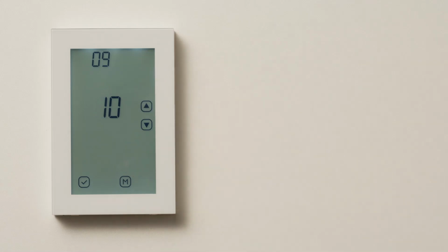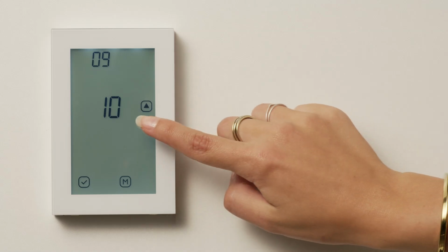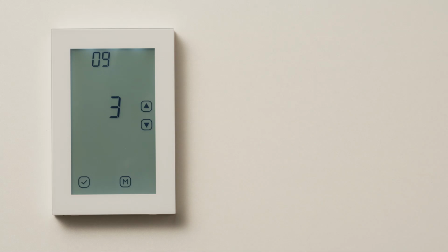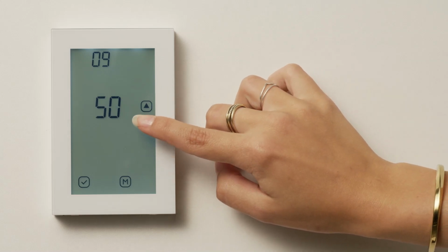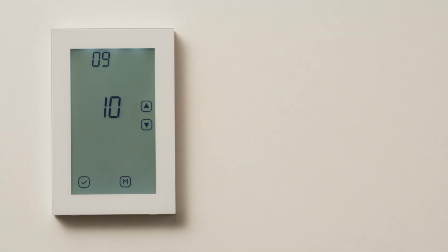09 is for a floor sensor setting. Parameter 01 should be set on F for parameter 09 to be relevant. Floor sensor type should only be set on initial install. Most modern thermostats have a floor probe set at 10 kilo ohms. Most Siemens thermostats have floor probes set at 3. The HT3 has 6 options for floor probe ohms, making it the perfect replacement. Incorrect setting will result in a temperature that is either too high or too low.